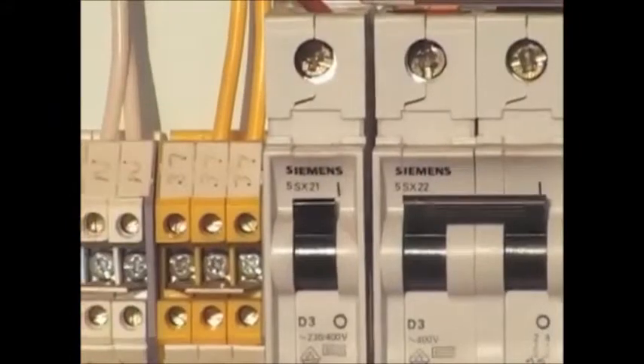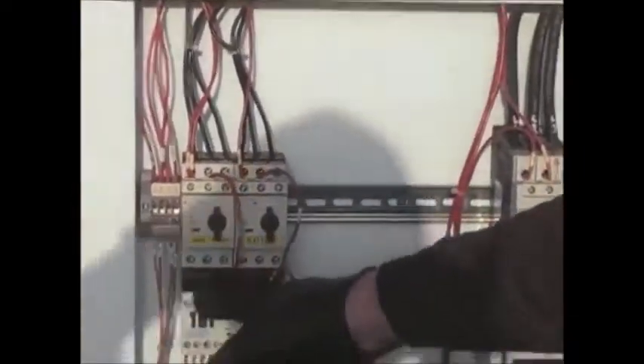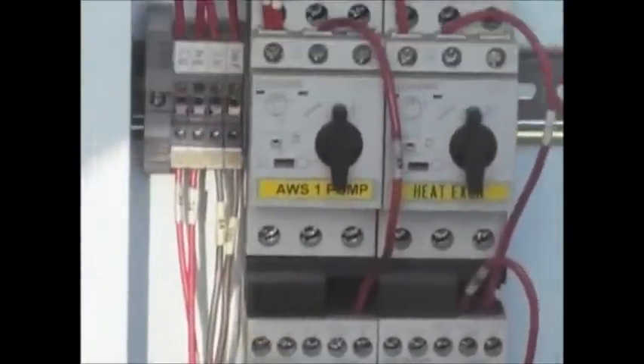I'm going to open this panel, and you'll see that there is no telemetry. Again, it's strictly a relay-based system. So you have main power coming in, which is wired now for 230-volt three-phase. It comes down and distributes to the appropriate things. Here are your circuit breakers for lights, outlets, and also for all your 110 control voltage. Again, all your relays that control the e-stop, your float switches, and then you have your motor starters: motor starters for the transfer pump, for your heat exchanger, SVE, and then your air Sparge.